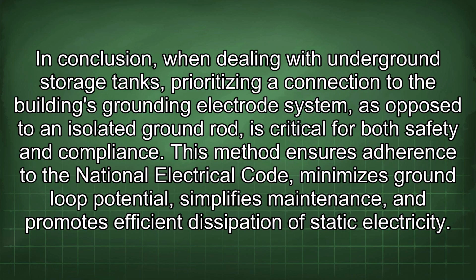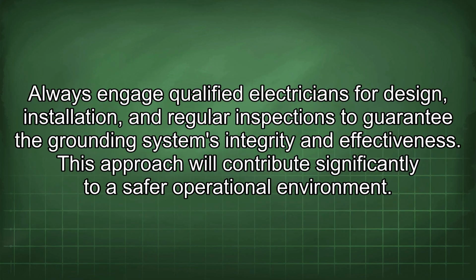In conclusion, when dealing with underground storage tanks, prioritizing a connection to the building's grounding electrode system, as opposed to an isolated ground rod, is critical for both safety and compliance. This method ensures adherence to the National Electrical Code, minimizes ground loop potential, simplifies maintenance, and promotes efficient dissipation of static electricity. Always engage qualified electricians for design, installation, and regular inspections to guarantee the grounding system's integrity and effectiveness. This approach will contribute significantly to a safer operational environment.